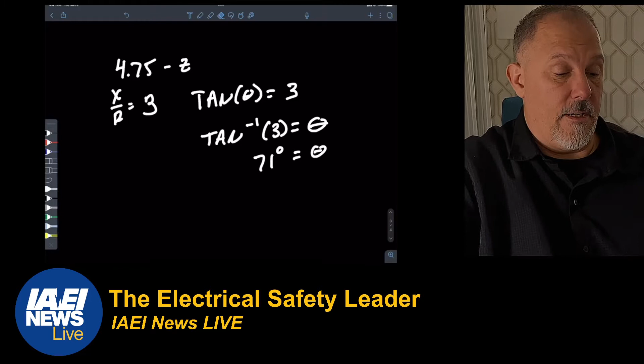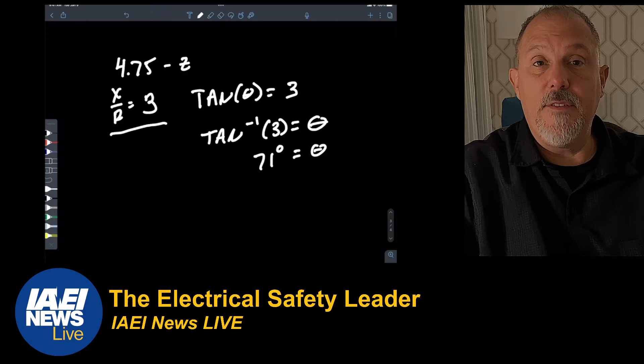So if I give you an X to R ratio, I am basically telling you what the power factor of the circuit, or the piece of equipment, or the system is at that point. So now I know 4.75 is Z. If I draw my triangle, this is 4.75. Because of the X to R ratio, I know this angle is 71 degrees. I have an R and I have an X. R is equal to 4.75 times cosine of 71.